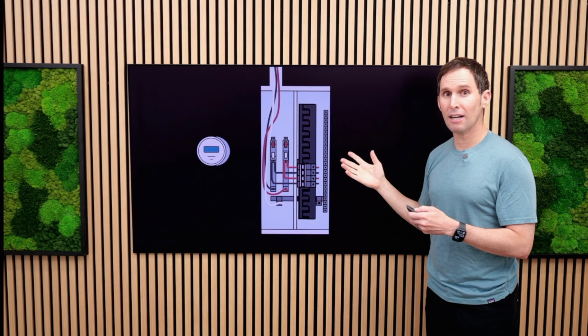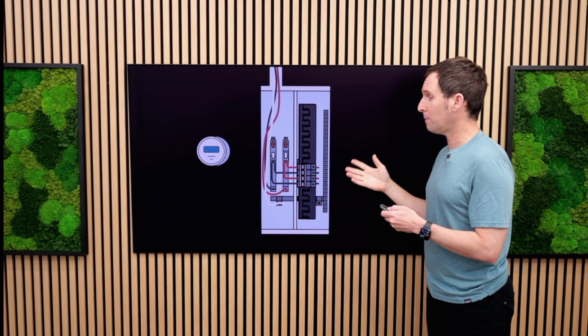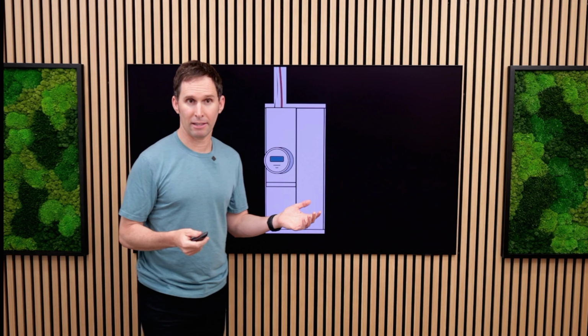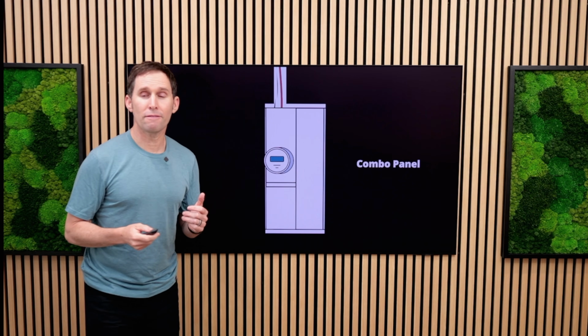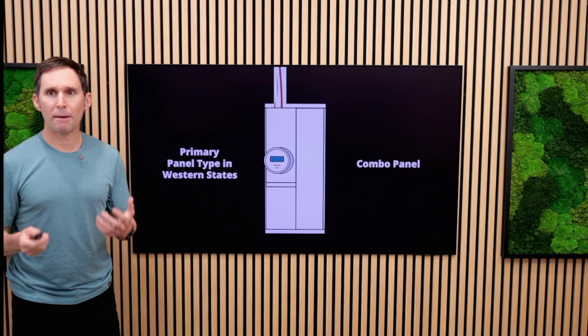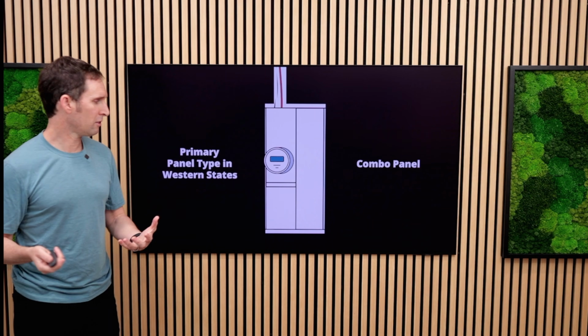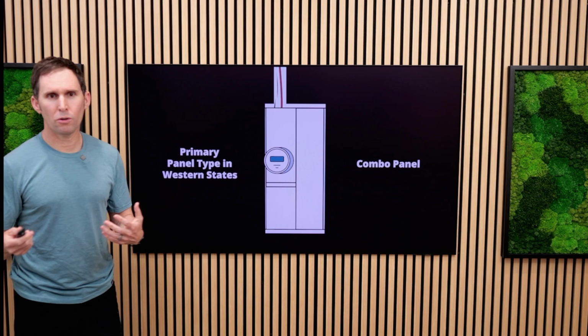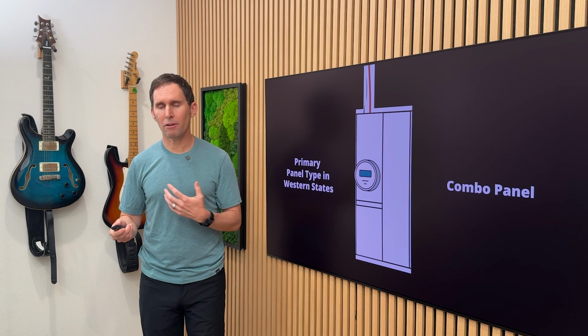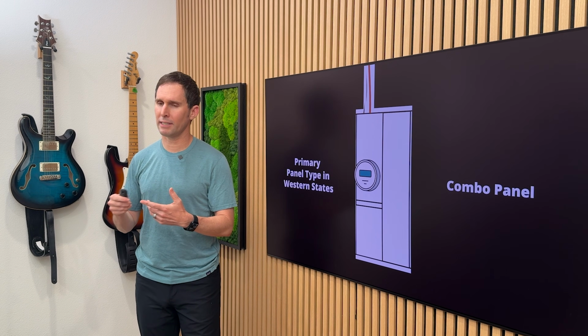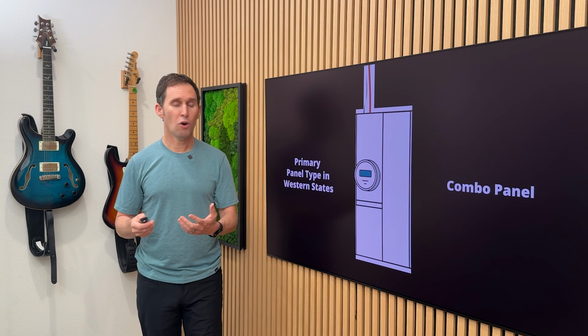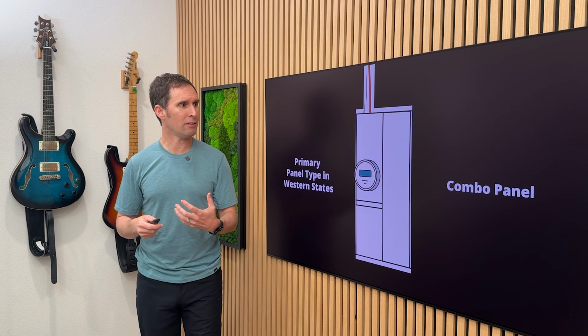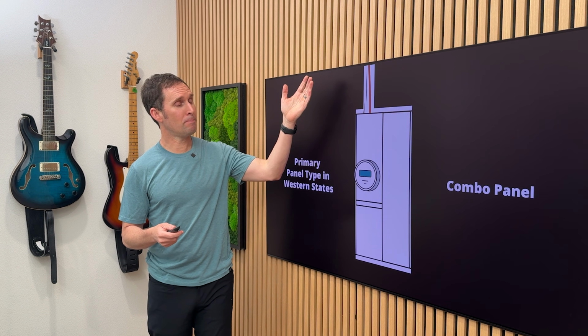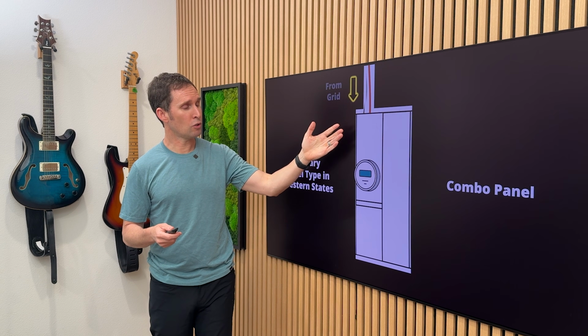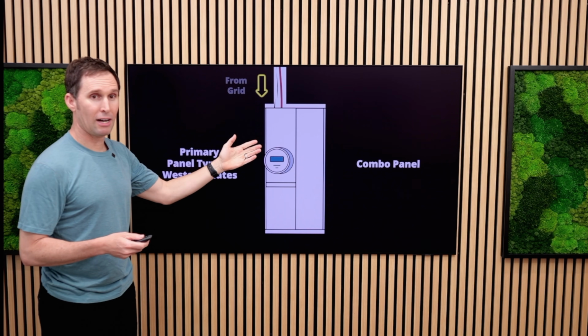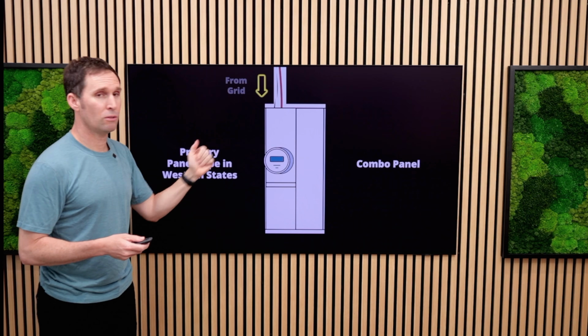This specific type of main electrical panel is called a combination panel. It's very common and the primary type of panel you'll find in the Western United States. Because of code and code adoption, this panel was primarily installed in most homes in California, Arizona, and Oregon, while the East Coast has a different type of panel. This panel has the power coming in from the utility directly to the meter socket, which then passes through the meter, and it's all in one.